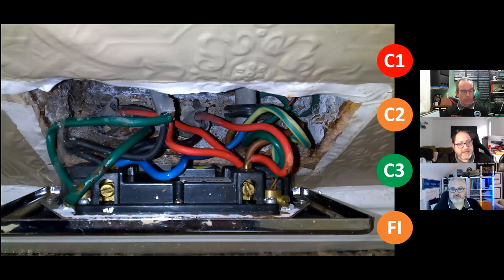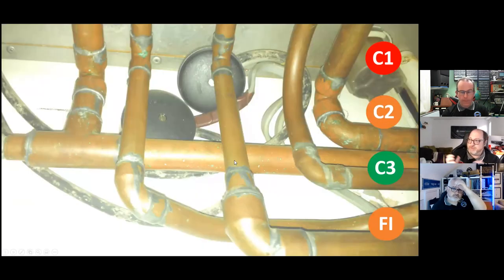Someone said here, so technically FI with every code. Well, the thing is, Mark, is how much time you've got for engineering judgment. Yes. If you can take the time to research the manufacturer to make sure the manufacturer's happy with 4x 2.5 mil cables to go in their socket, then you can tick that. If you don't, then that's the point. Do we ignore it or do we then put extra work? And I can completely understand that with regards to how rapid we have to do these days, this kind of work just doesn't sound doable.